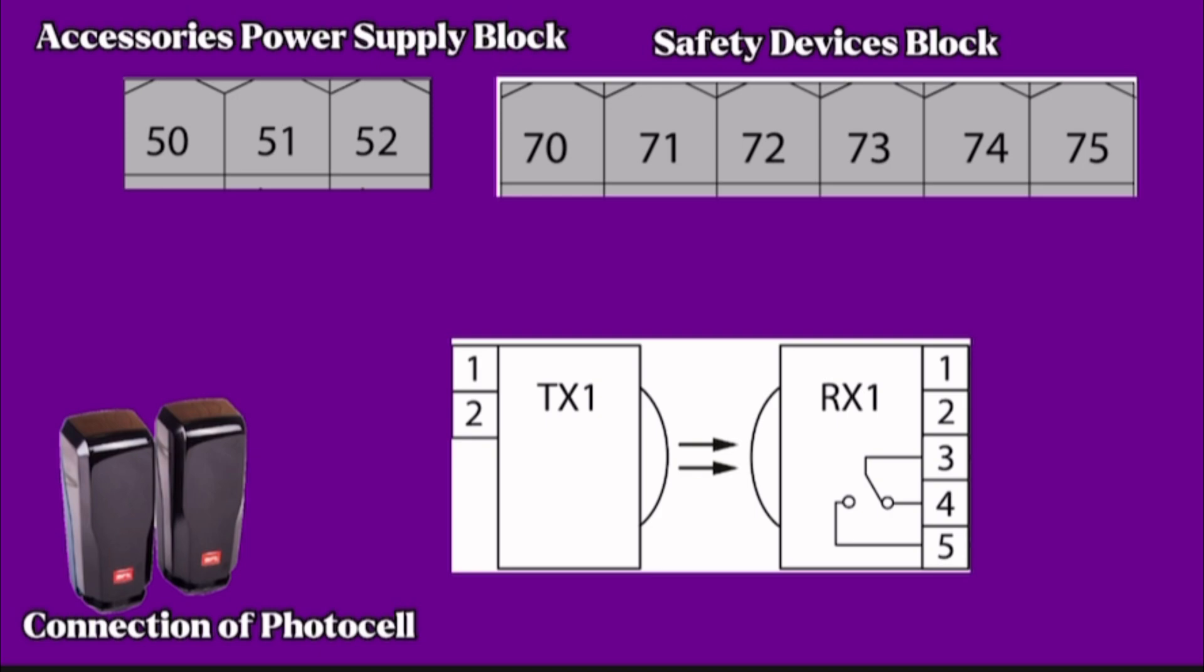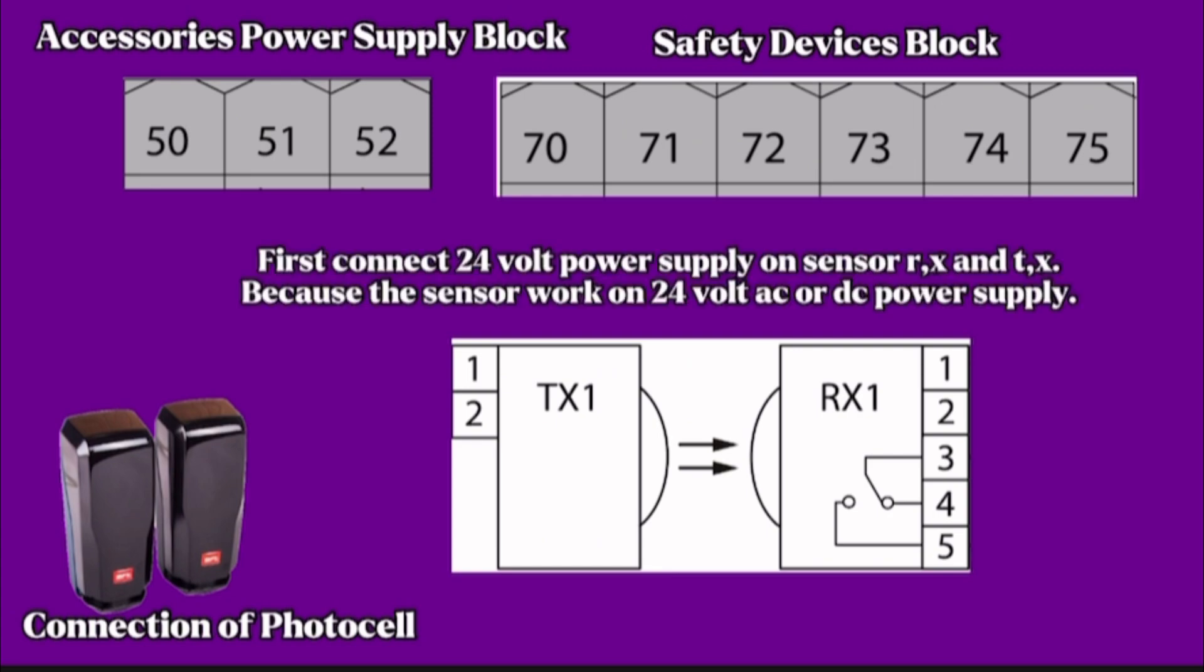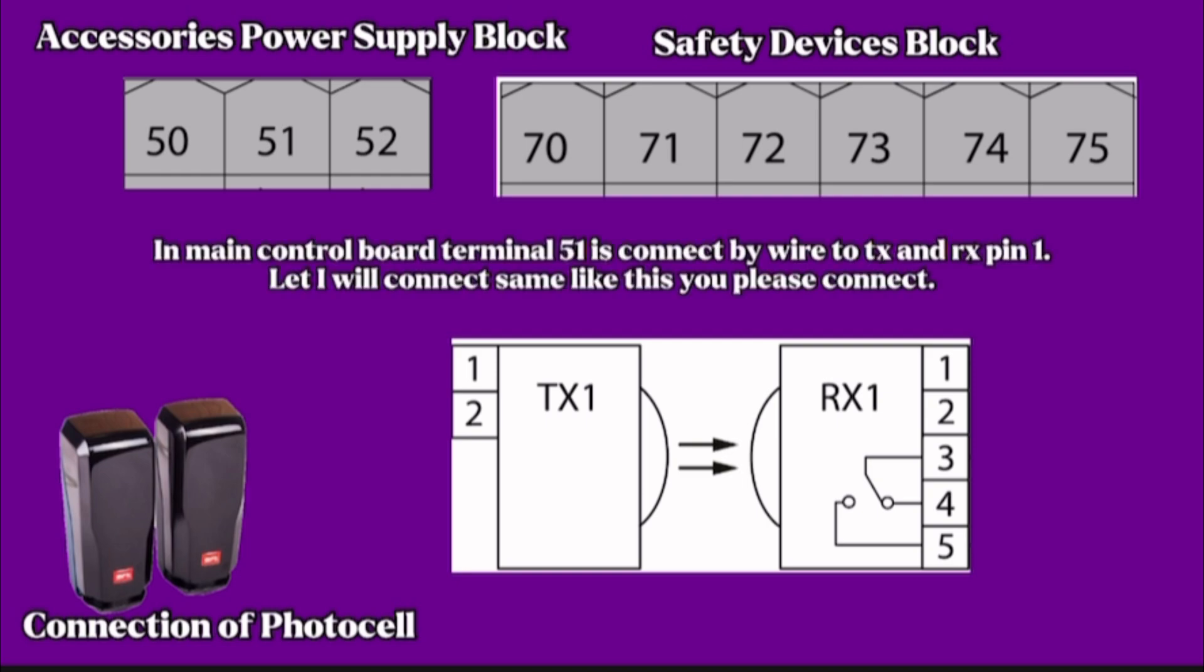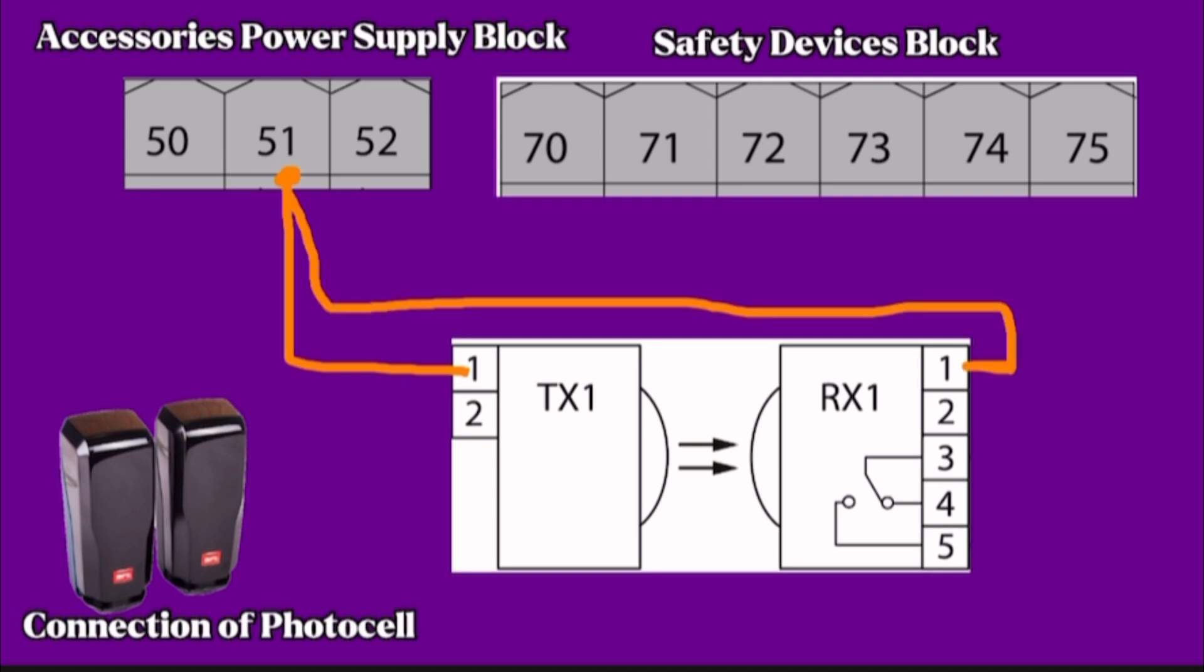This single pair of sensors - one transmitter, one receiver. First connect 24-volt power supply on sensor RX and TX because the sensors work on 24-volt AC or DC power supply. Take power supply for sensors from control board. In main control board, terminal 51 connects by wire to TX and RX pin 1. Pin 51 is output power 24-volt AC.